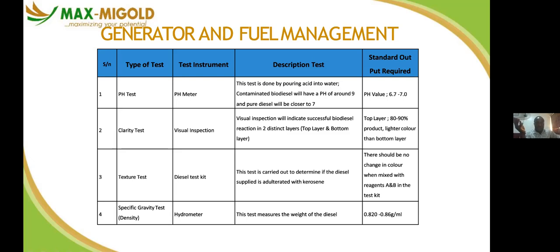Then specific gravity, which is also the density, you use a hydrometer to do that. There's a range value set for good diesel. Within this value, the diesel can perform very well, and the generator can perform very well. The range is 0.820 to 0.86. Most times we get 0.84 to 0.85, from most of the records I have. I believe most of you are also within this range, 0.84 to 0.85. Are we together? That's the standard. So anything short of this, don't accept the diesel.